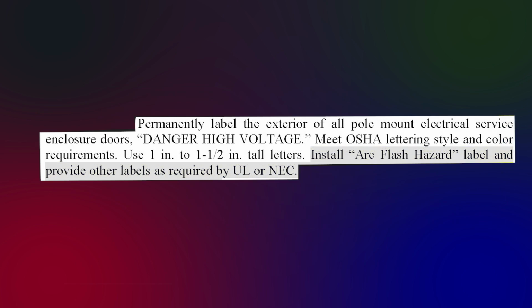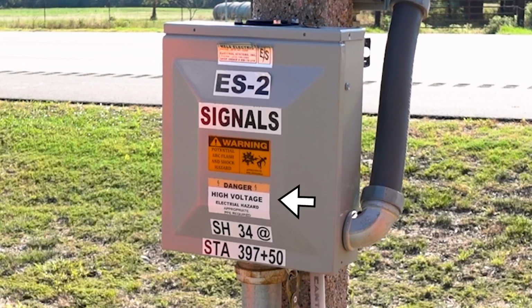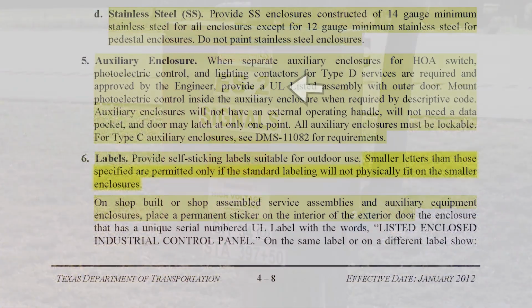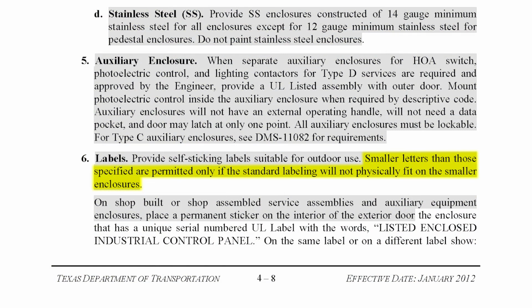At first glance, we might think this completes the Type T specification, but DMS 11080 also specifies requirements for all services, which include labeling. The front cover of the load center must have a danger high voltage label, an arc flash hazard label, a label identifying the load served by the service, and a unique service ID that matches the electrical service data chart from the plans. DMS 11080 also allows that when a label with 1-inch high letters is too big to fit on the enclosure door, then smaller-sized letters may be used.